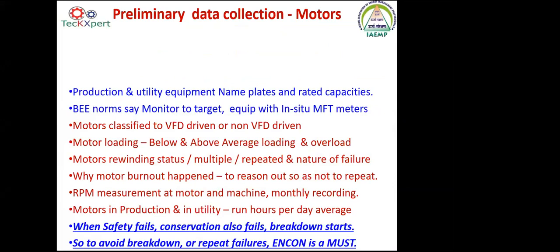Next, please. Yeah. So in the primary data collection, to start with motors, as I said, for any production equipment or any utility equipment, the nameplate and rated capacities have to be jotted down, and be there as a ready reckoner at your fingertips, especially in the energy audit analysis. Bureau of Energy Efficiency always says monitor to target. Equip all your equipment with in situ multifunction meters if it is more than 20 HP or 30 HP or critical equipment. Any equipment needs a basic kWh meter and a run-hour meter if it is run intermittently.